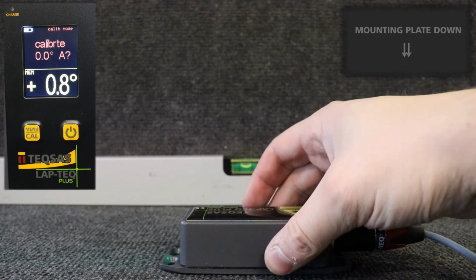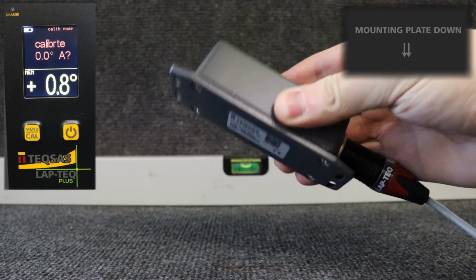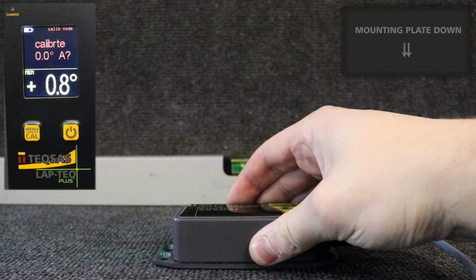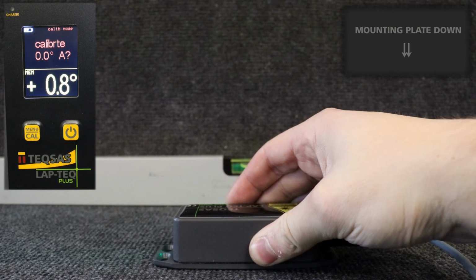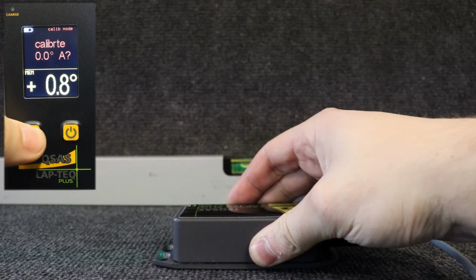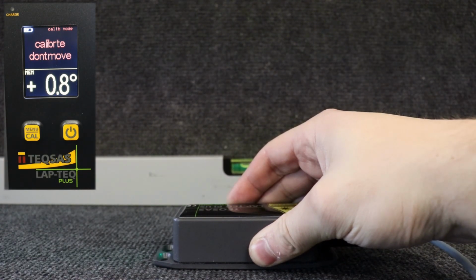The first calibration cycle is for mounting plate facing down, the label with the writing facing up. This is the default mounting position. Each calibration cycle has 4 steps. For step 1, position the sensor horizontal at 0.0 degrees and press the Cal button. The display shows Don't Move while the calibration measurement is happening.